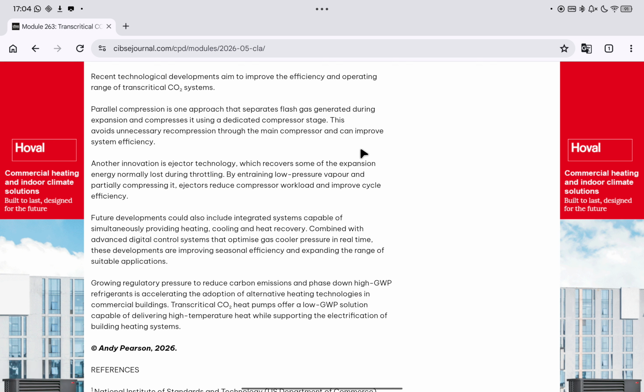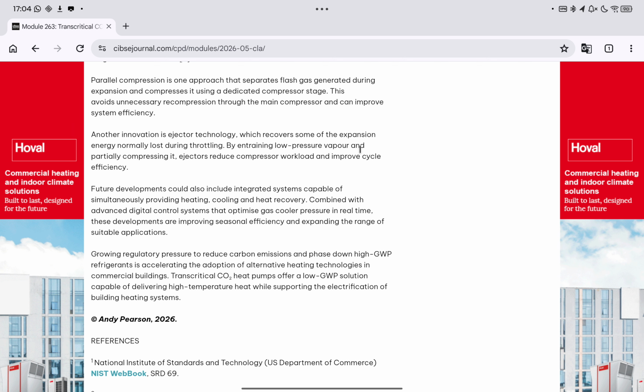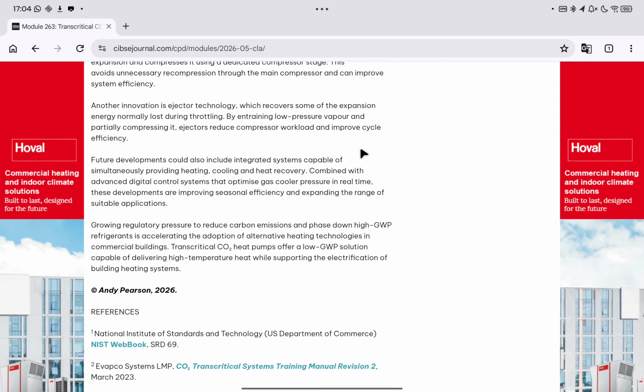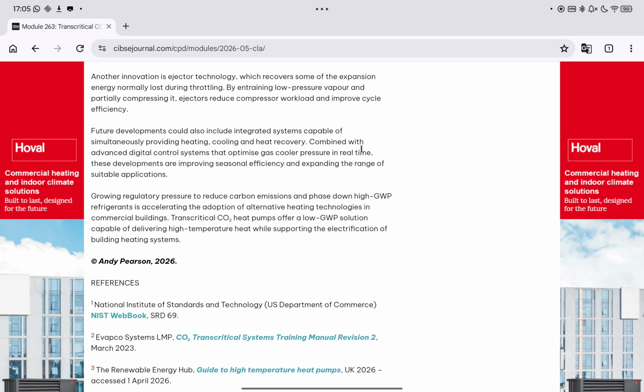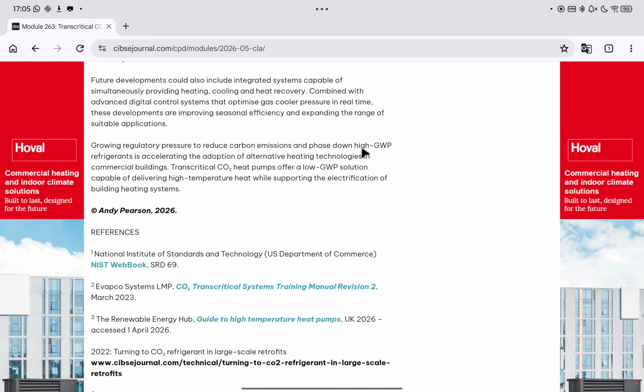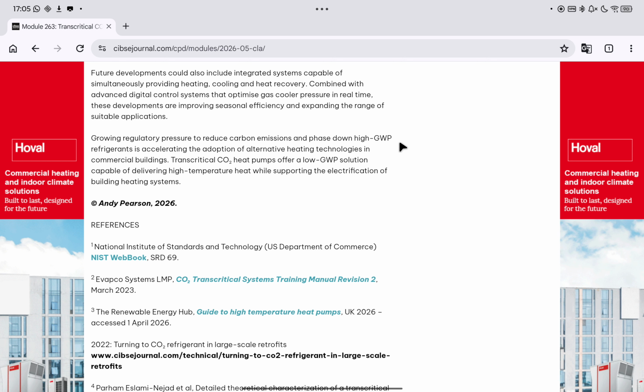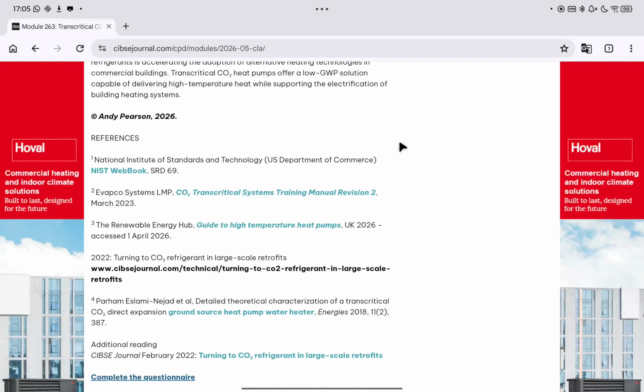Future developments could also include integrated systems capable of simultaneously providing heating, cooling, and heat recovery. Combined with advanced digital control systems that optimize gas cooler pressure in real time, these developments are improving system seasonal efficiencies and expanding the range of suitable applications. Growing regulatory pressure to reduce carbon emissions and phase down high GWP refrigerants is accelerating the adoption of alternative heating technologies in commercial buildings. Transcritical CO₂ heat pumps offer a low GWP solution capable of delivering high temperature heat while supporting the electrification of building heating systems.